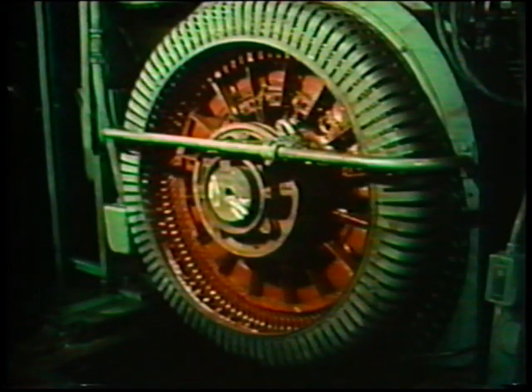In this unit, we're going to be talking about synchronous motors and their controllers. Synchronous motors have several features. They operate at a constant speed, and they can be used to improve the electrical efficiency of an industrial operation.